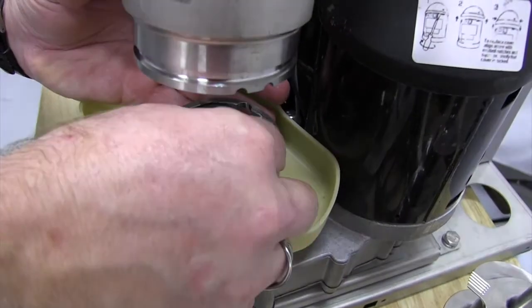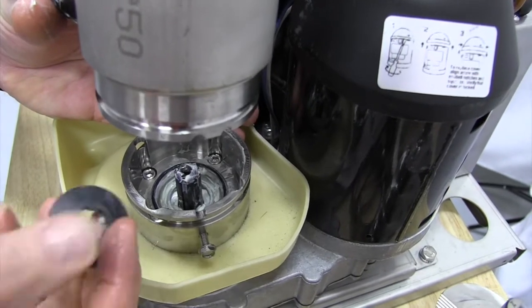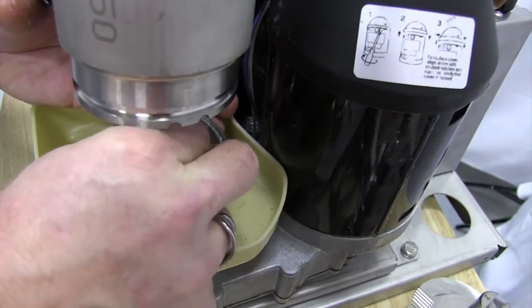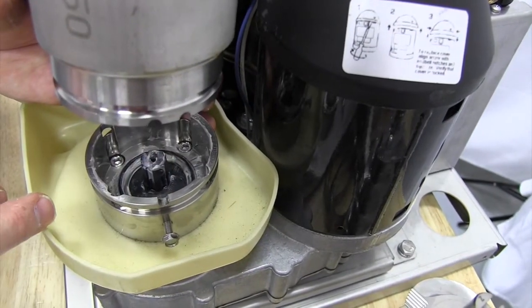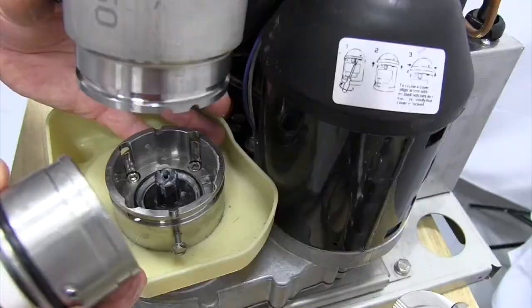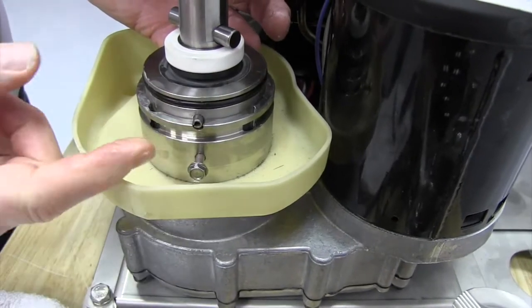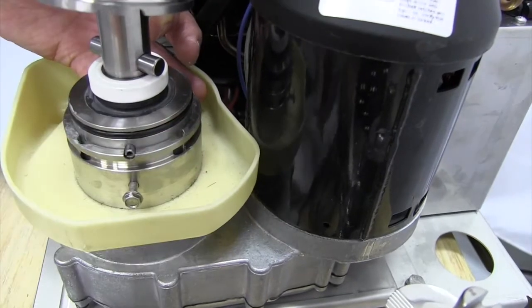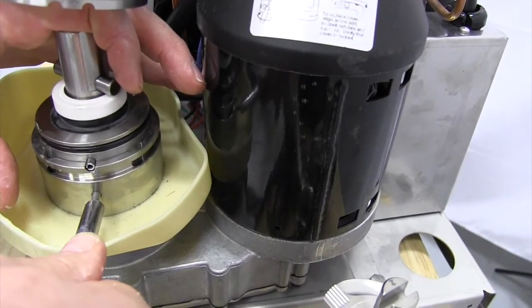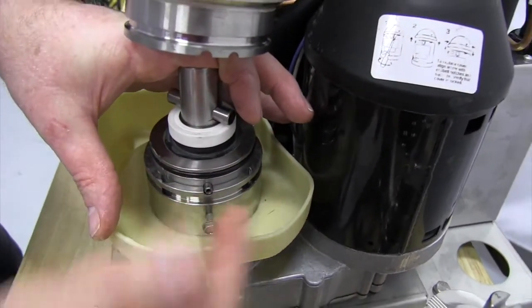So reassembling, we've got our O-ring. We're going to put that down into the O-ring groove. Again, that O-ring is what's going to seal out condensation from getting into our bearings. We can put some fresh food-grade grease down in the well, down in there where the output shaft comes out. This is what we call our condensate shield - that's going to go down over the output shaft to help keep some of the cold from the evaporator from making it back down into the gear motor. We've got our bearing, put that onto the output shaft, and we're going to rotate it around so that our roll pins line up with the notches. What we're going to do is push down on the bearing as we tighten up the set screw to make sure that O-ring is seated very well.